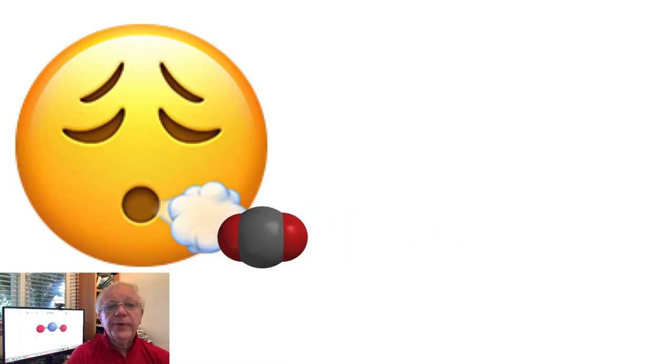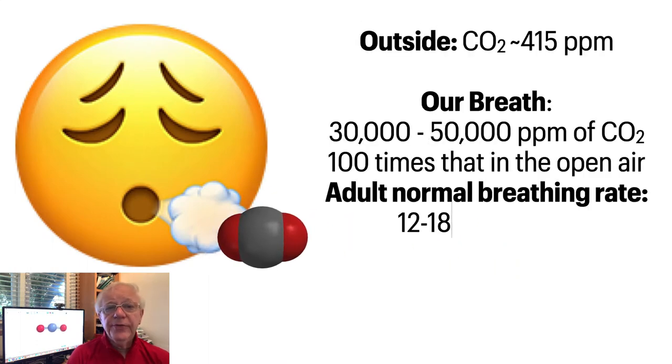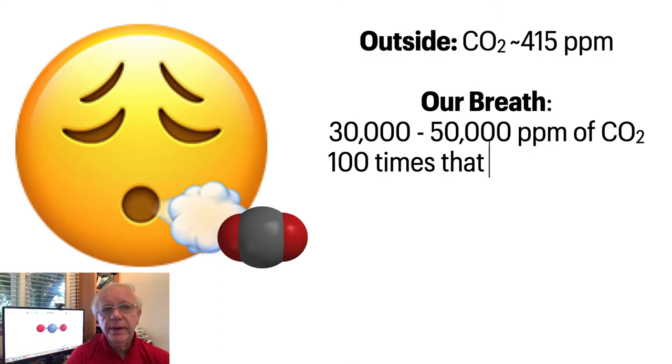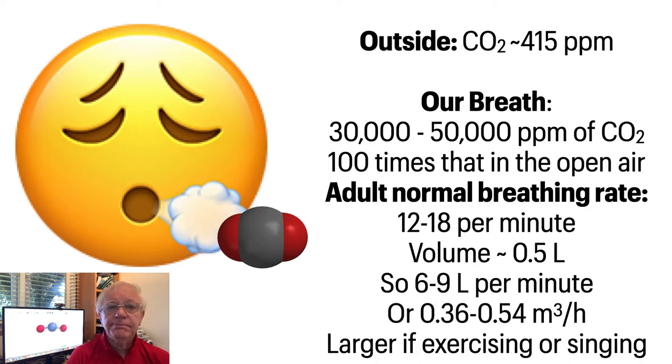The air we breathe out contains something like 30,000 to 50,000 parts per million of CO2, about 100 times higher than in clean air. As a result, we can estimate how much CO2 will be exhaled by, for example, a healthy adult breathing normally and that works out to be about 360 litres per hour.